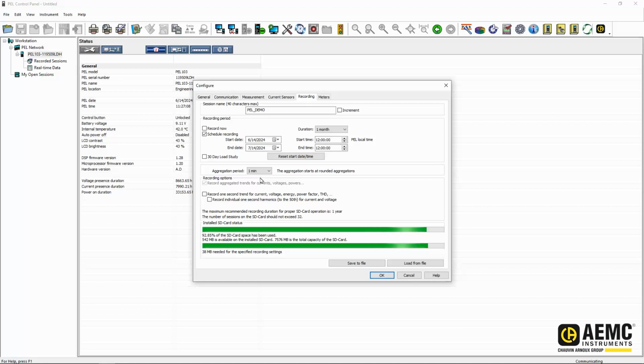Below aggregation, we can also enable 1-second trends for our recording. 1-second measurements will appear in a separate stored location in our data file and provide significantly better granularity for troubleshooting applications like measuring longer lasted voltage disturbances. Like the aggregation period, 1-second trend recordings will be an average of the measured values for a 1-second period. Here I've selected a 1-minute aggregation period and 1-second trends to be recorded.